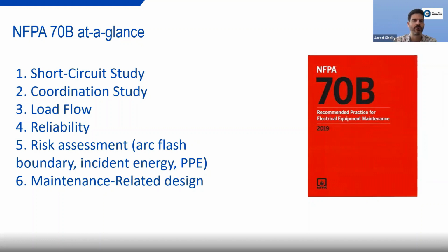So I guess if I'm hearing this correctly, NFPA 70E is mandatory, you have to do it. NFPA 70B is highly recommended for optimal equipment reliability. Yes, that is correct.